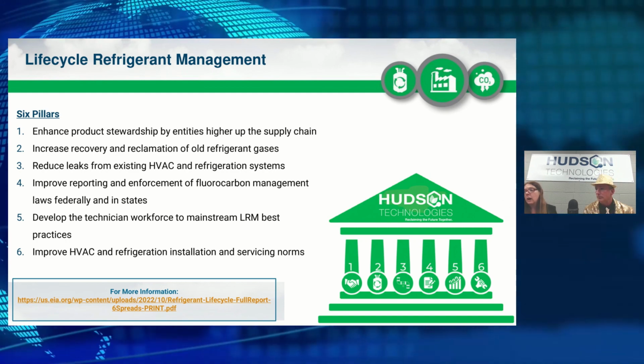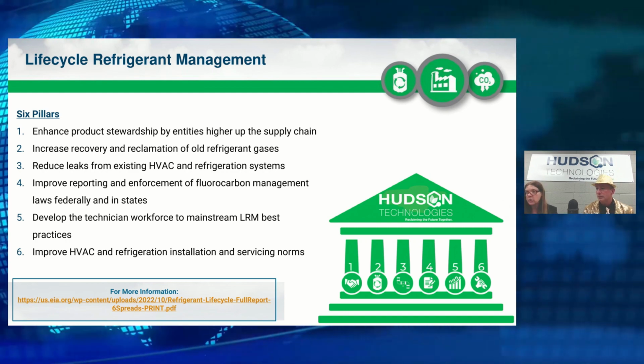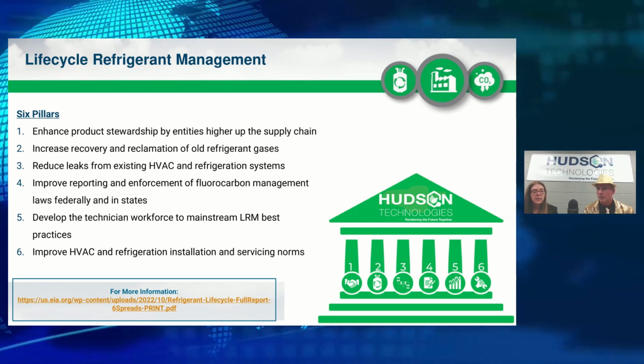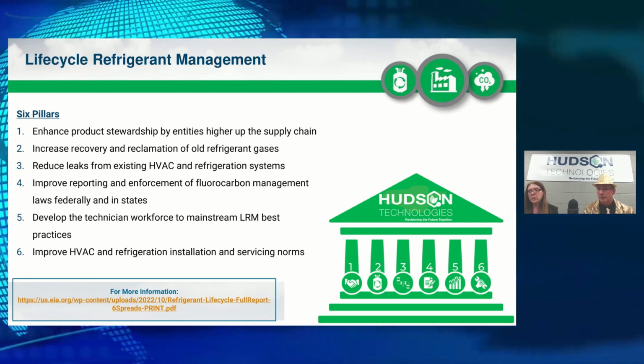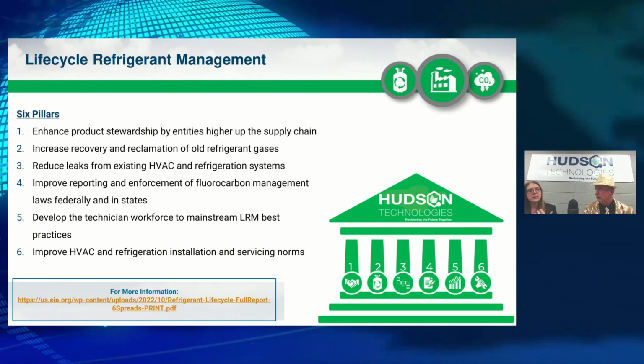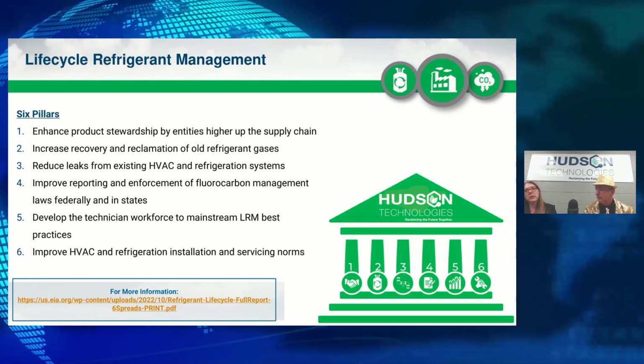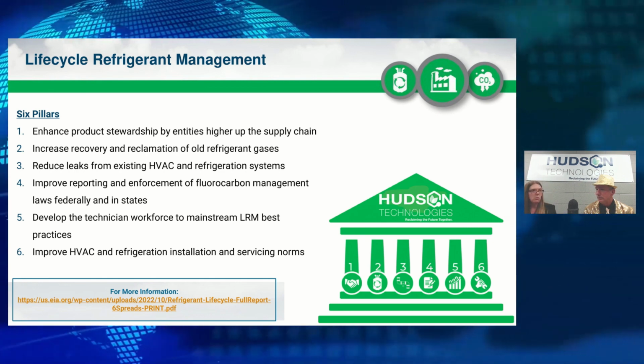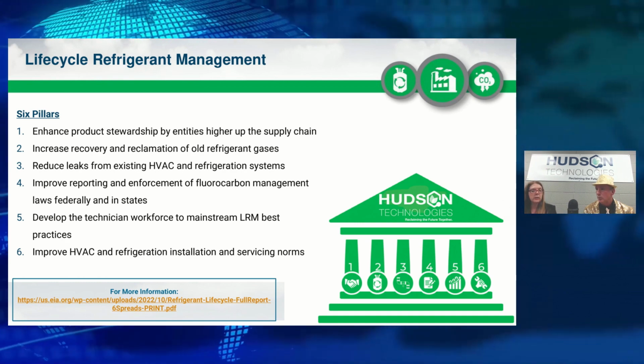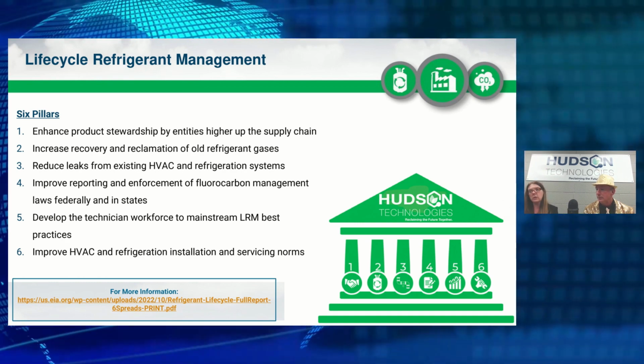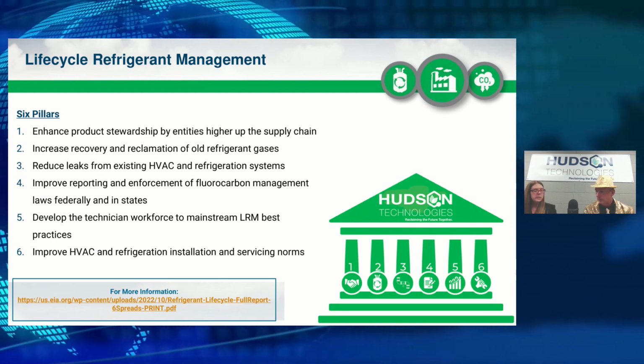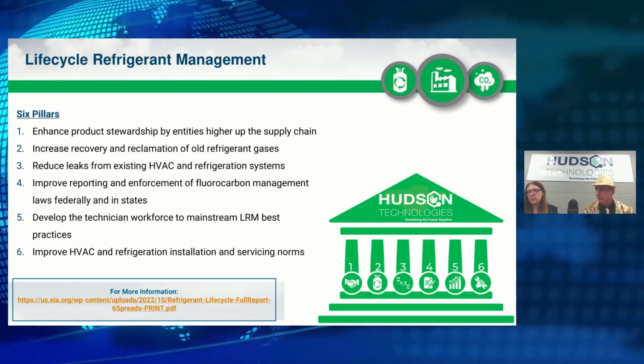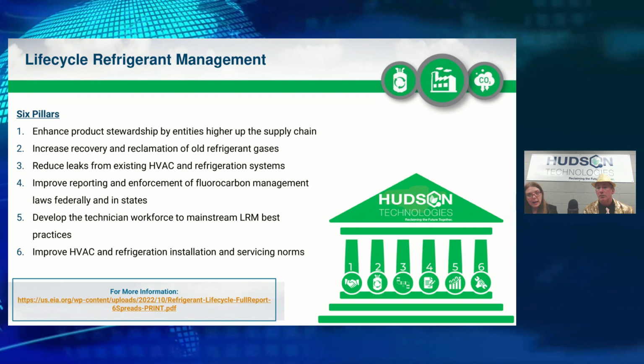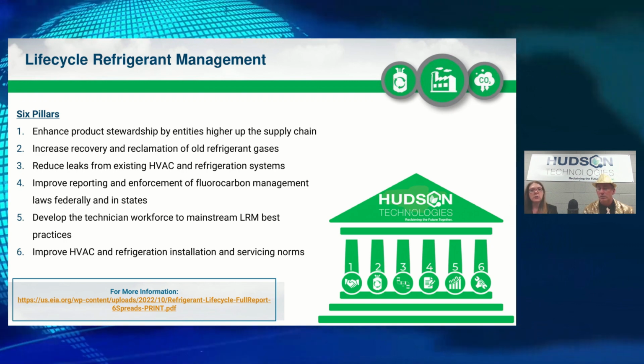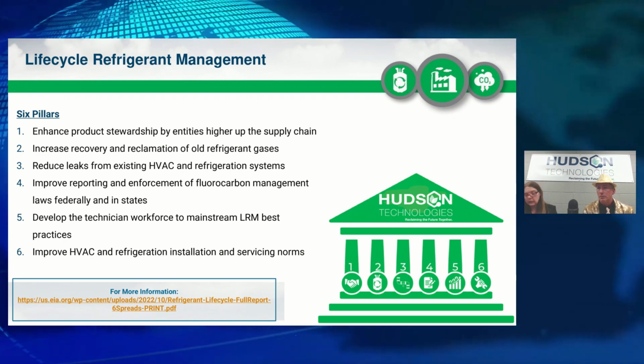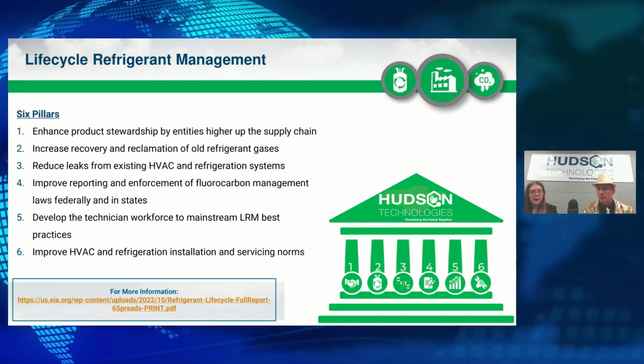So what California and other states are starting to do is say, I know that we're going to put the technology transition rule into place, but because of the HFC phase down, we're going to escalate this so that after January 1st of 2025, you cannot buy virgin refrigerant in the state of California. You're going to have to buy reclaimed refrigerant that has been reprocessed to the AHRI 700 standard so we can use our service gas to go back into service.